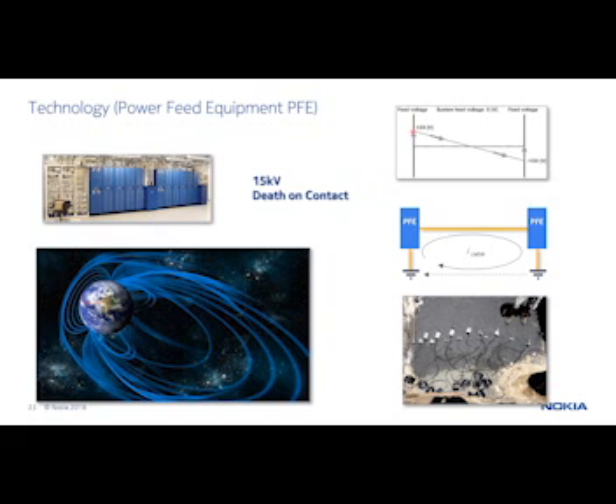So we power this across the submarine cable system. One power feed at one end would be, say, a positive voltage, the other one would be a negative voltage. So you could go plus 15,000 volts here, minus 15,000 volts there. Across the cable, you have a total of 30,000 volts, and we leverage the earth as a return path.